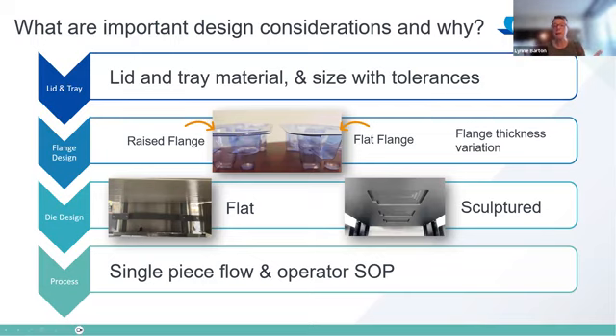And when a flat flange tray is used, higher tolerance can create greater misalignment. So if you have a Tyvek lid, that can result in fusing of the lid to the tray, and that can delaminate during the opening process, like those pictures that Jeremy showed in the very beginning. That's one example of what can happen when you have a flat flange tray and a Tyvek lid and not great alignment. Maybe you don't have a little extra material overhanging and that lid can fuse. Raised flanges have that unsealed area around the perimeter of the tray, around the flange, so misalignment becomes a little less risky. That's why all of us like to see those raised flange trays.